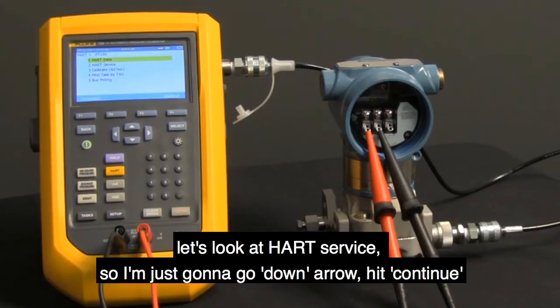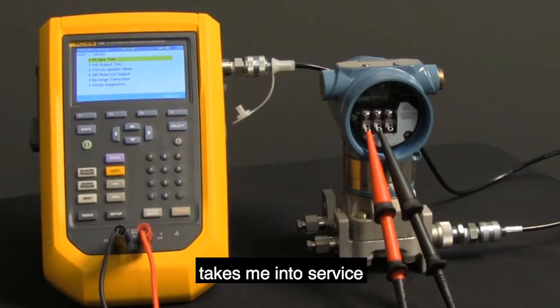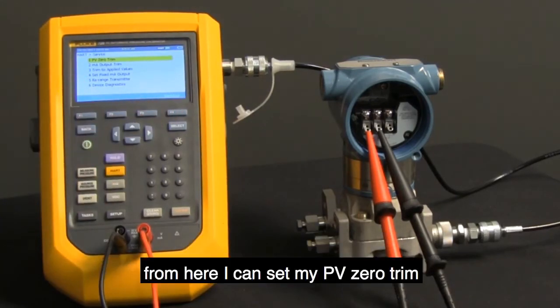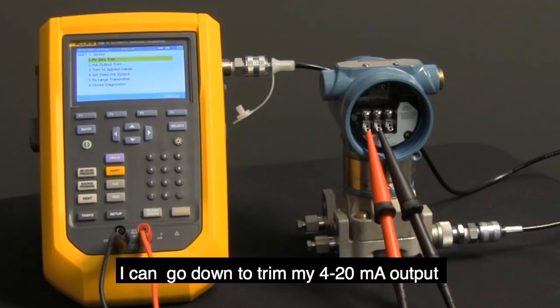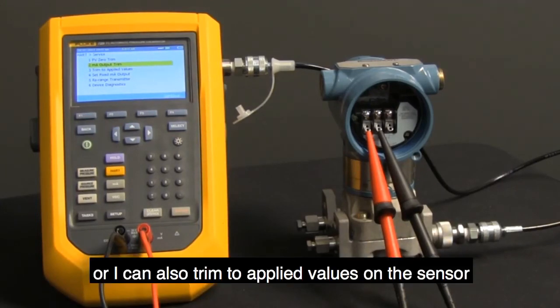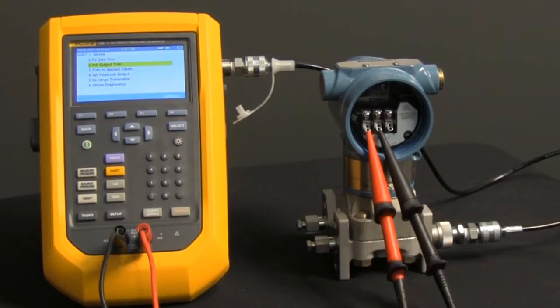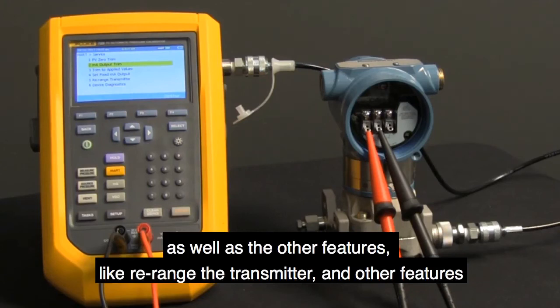Let's look at HART service. I'm just going to press the down arrow, hit continue, and it takes me into service. From here, I can set my PV zero trim, go down to trim my 4-20 milliamp output, or trim applied values on the sensor, as well as other features like re-ranging the transmitter.